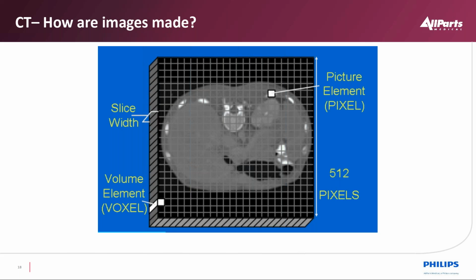The image is not just a flat image, it has depth to it. When we do a 5mm slice or 10mm slice, we're averaging all the detail in that cut. As we get thinner cuts on a CT scanner, as we page through these images, it better represents what the anatomy is on the Z-axis. We're looking at X and Y here, and Z has depth. One of the things we look at on the screen of a CT scanner is how the data was collected, which algorithm was used, the slice thickness, the kV and mA. All of that is displayed.